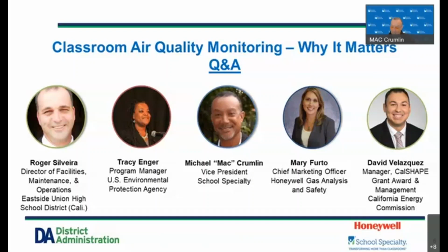So you are going to see quite a bit of variation in quality across manufacturers. I'm not aware if an independent study was done yet. That's definitely something that we could work with a third party to set up. What I would recommend, though, we typically see variation around 40 to 50 ppm in our devices. That's within the California guidance of 50.